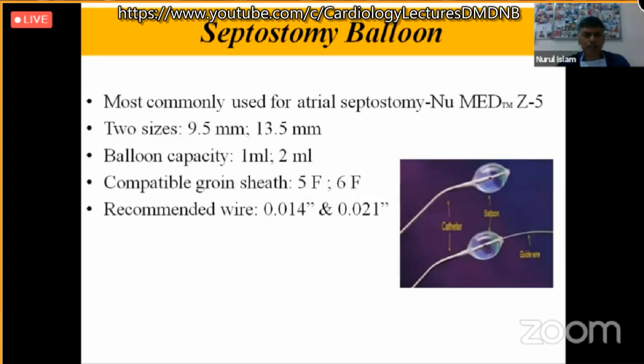The septostomy balloon is used especially for congenital cyanotic heart disease — specifically transposition with intact septum — and is a life-saving procedure. Two sizes are available: 9.5 mm and 13.5 mm with balloon capacity of 1 ml and 2 ml. Inflating with 2 cc of diluted contrast achieves the maximum 13.5 mm size for larger babies. The recommended guidewire is 0.021 inches.